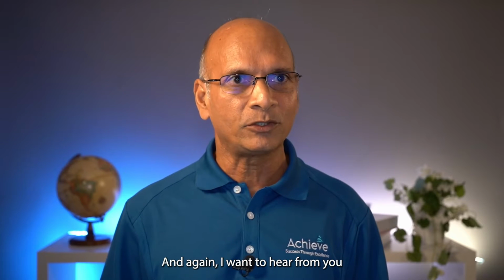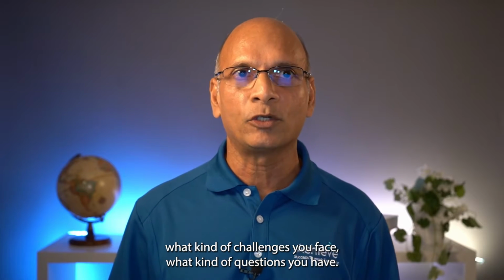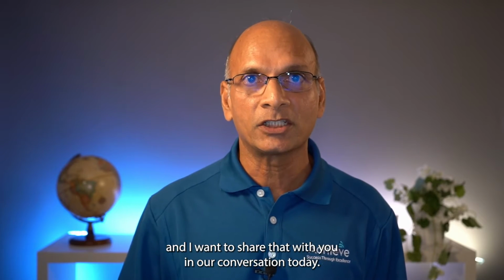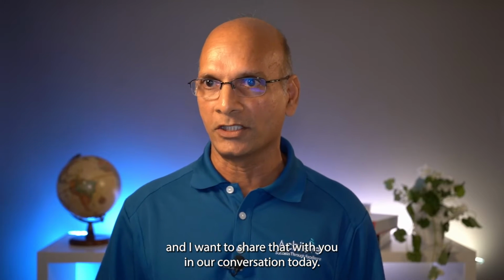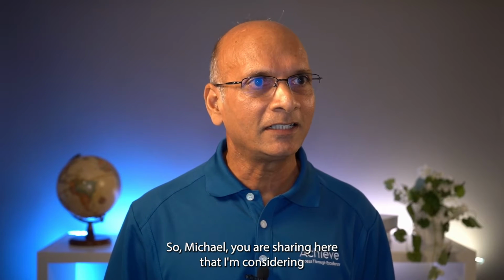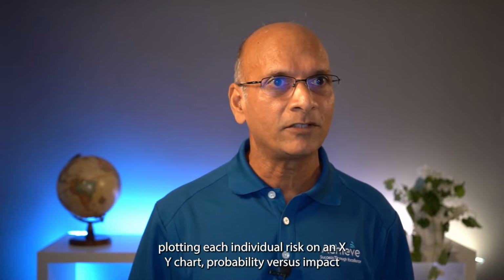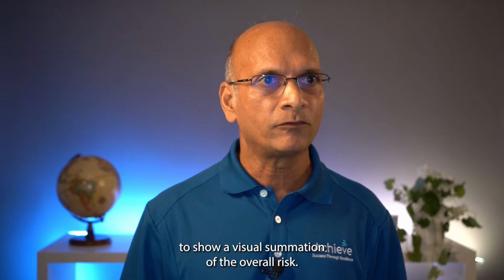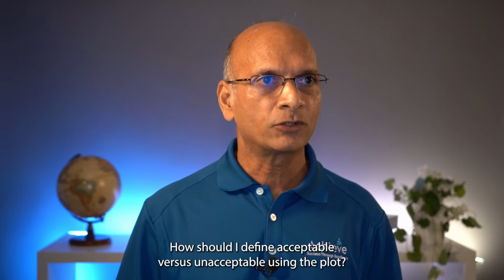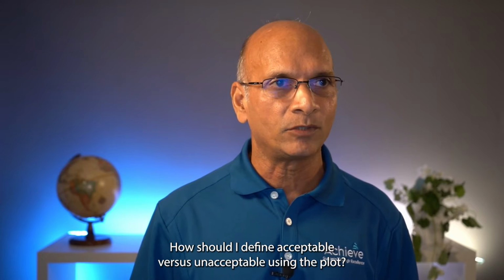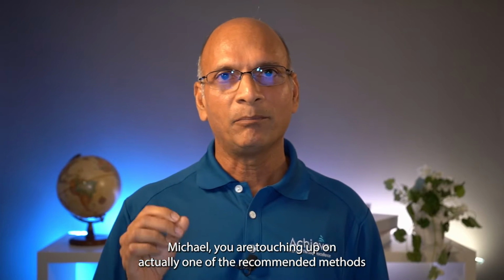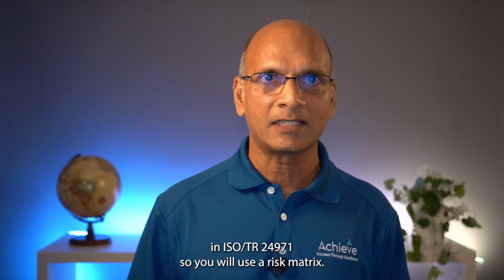Again, I want to hear from you what kind of challenges you face, what kind of questions you have. Some of you did submit a few questions and comments at registration, and I want to share that with you in our conversation today. So Michael, you are sharing here that I'm considering plotting each individual risk on an XY chart, probability versus impact, to show a visual summation of the overall risk. How should I define acceptable versus unacceptable using the plot? Michael, you are touching upon actually one of the recommended methods in ISO TR 24971.